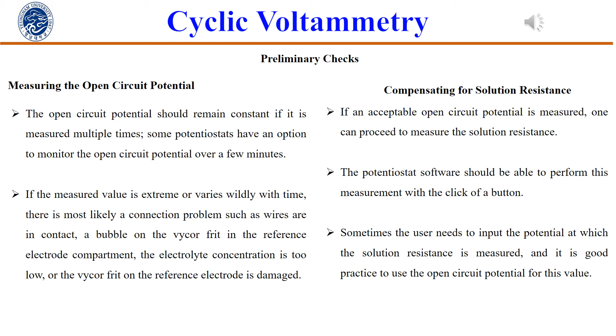One way to minimize the solution resistance, limiting the amount of compensation required by the potentiostat, is to place the reference electrode and working electrode as close to each other as possible without contact, so that we can minimize the solution resistance. After preliminary checkups, we need to look at some important parameters, that is solvent window and scan rate.